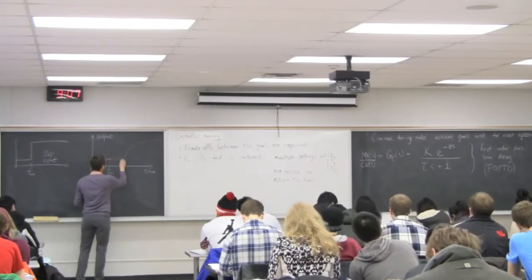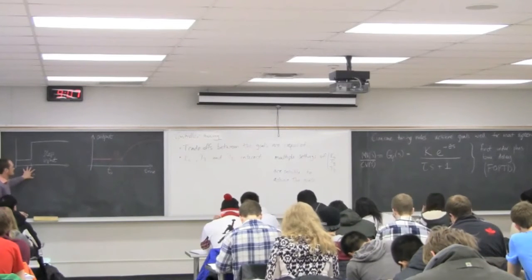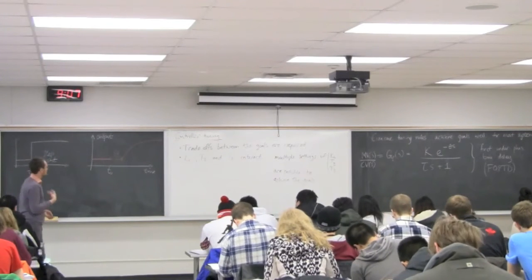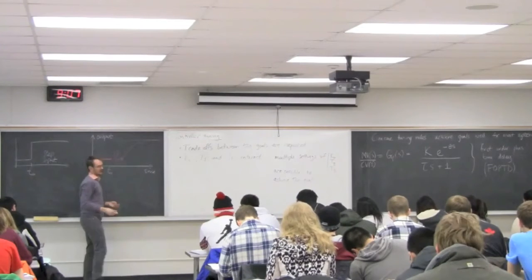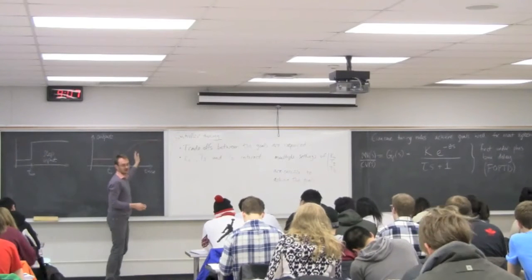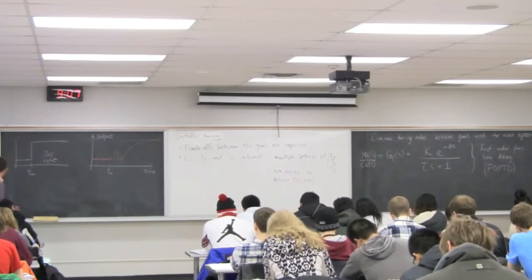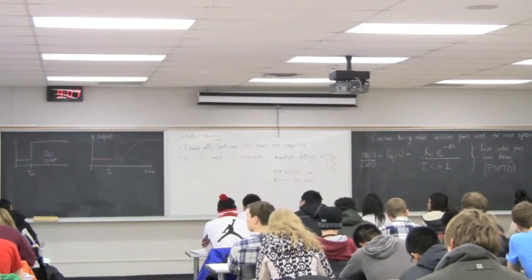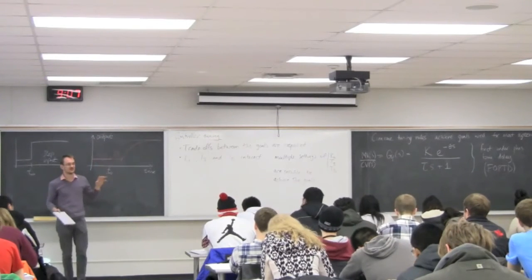So this time that is spent over here, we call theta, is my time delay. I put my step input at t0, I'll only see an output delayed by theta units of time. There's some time constant then that tells me how I rise up to achieve that final output. So tau then tells you how quickly you ramp up here to achieve the final goal. Okay, so it seems like a fair oversimplification. But this first order plus time delay process actually represents many real systems in practice.